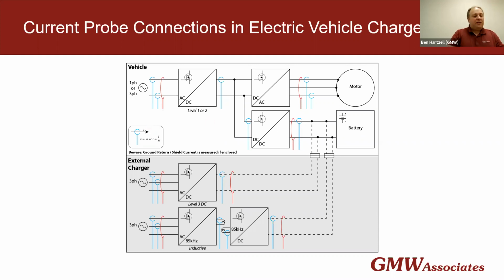All the probes we're talking about today are analog probes with either a voltage signal equal to the sensitivity times the primary current, or a secondary current output signal equal to the primary current divided by the number of turns. I'll get into the details of both types later.